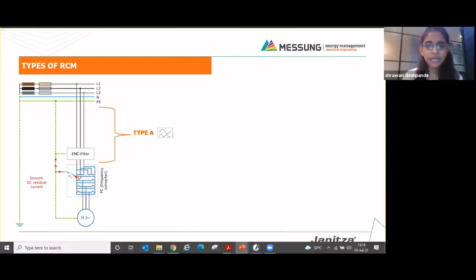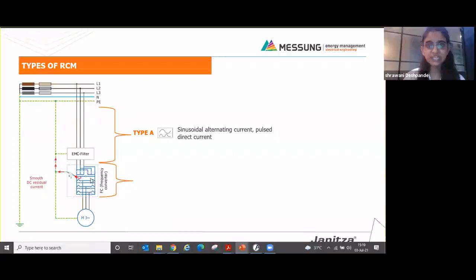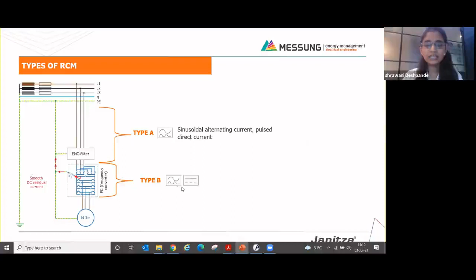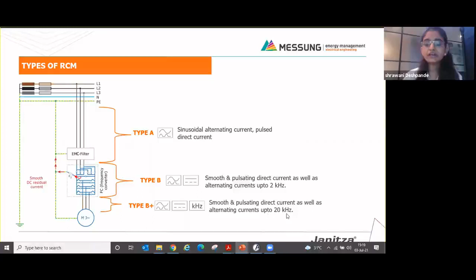Type A includes sinusoidal alternating current and pulsating direct currents. Now, if my failure occurs inside the VFD, meaning due to some failure of switching devices or anything happening inside the VFD, then my residual current would be of type B. Type B includes smooth and pulsating direct currents as well as alternating currents up to 2 kilohertz. And if my fault occurs outside the variable frequency drive, then my residual current would be type B+. B+ includes smooth direct current and alternating currents up to 20 kilohertz.